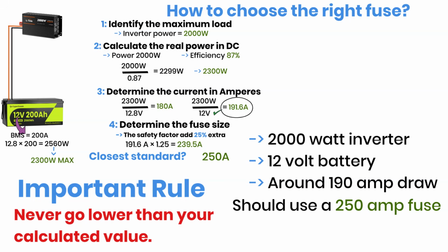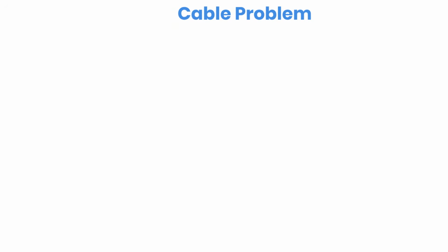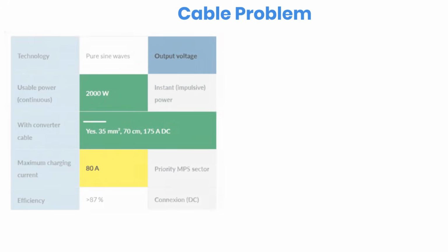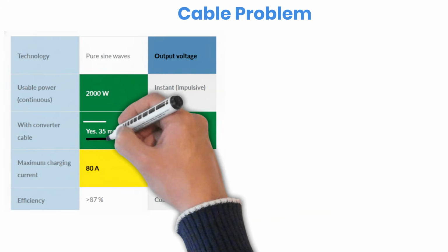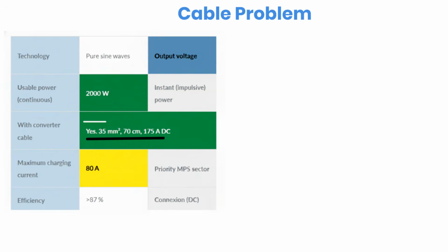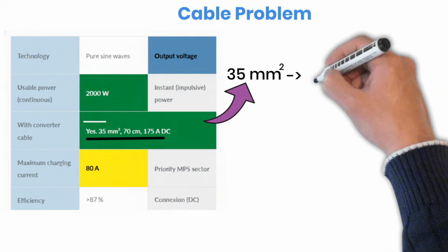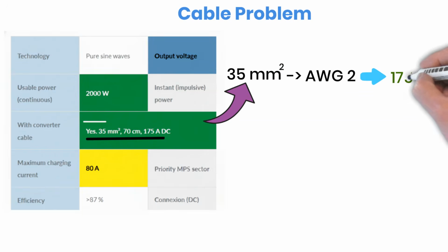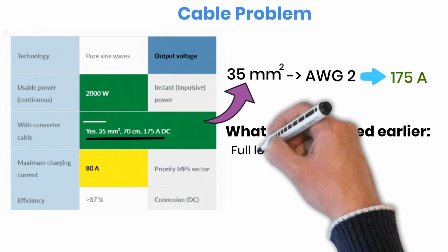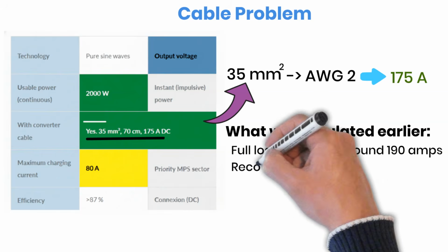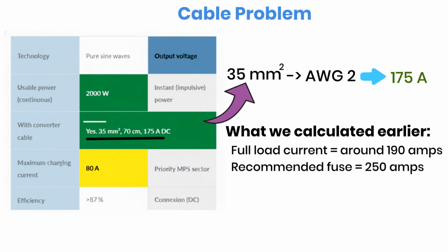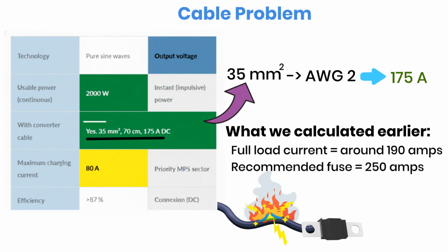Now this is where most people make a serious mistake. Cable problem. Let's say your inverter comes with cables. In many cases, you'll see something like 35 square millimeter cables. Sounds good, right? But here's the issue. Those cables might only be rated for around 170 to 175 amps. Now remember what we calculated earlier. Full load current equals around 190 amps. Recommended fuse equals 250 amps. See the problem? If you keep those smaller cables and install a 250 amp fuse, your fuse will not protect the cable anymore, because the cable will overheat before the fuse blows.